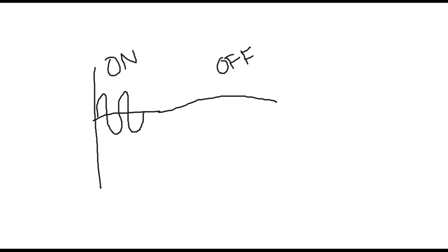They're electrically stimulated, and they have what's called the piezoelectric effect, and we'll learn about that later. It goes from electrical to acoustic. What's reflected back from the body is acoustic, and it gets transferred back to electrical. Right now, we're just looking at our pulse, the electrical pulse that's stimulating the crystals, and it's going to produce a sound wave.